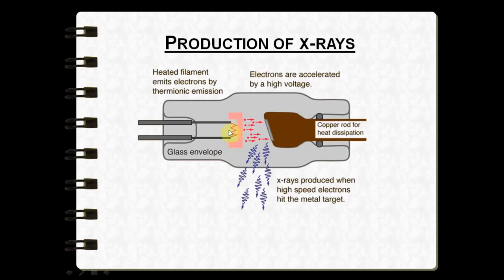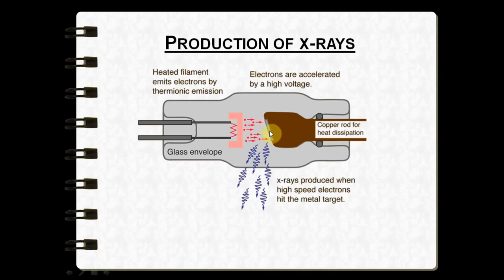Once the filament is heated, it undergoes thermionic emission and an electron cloud forms in the focusing cup. When the exposure button is pressed, the high voltage circuit is activated and this electron cloud is accelerated across the x-ray tube, hitting the target on the anode. When the electrons strike the tungsten target, kinetic energy is converted to x-ray energy and heat — 99% is dissipated as heat, carried away by the copper stem and absorbed by the insulating oil.